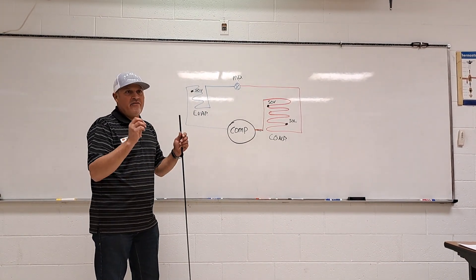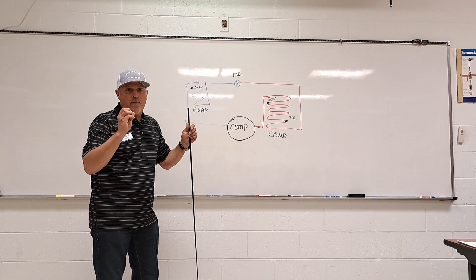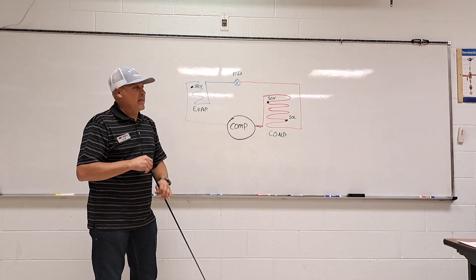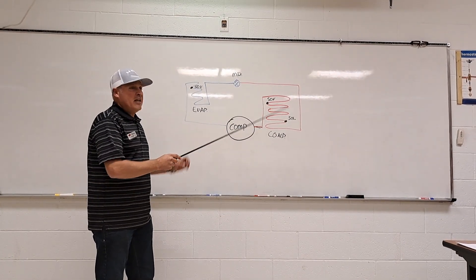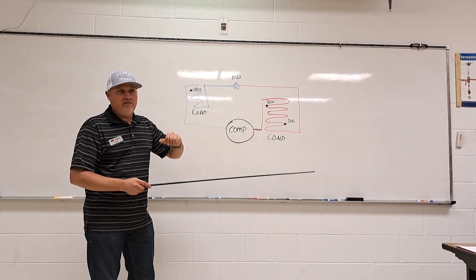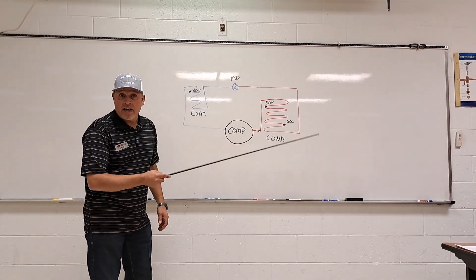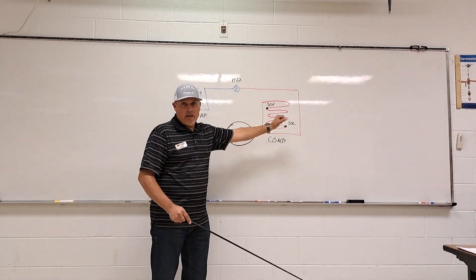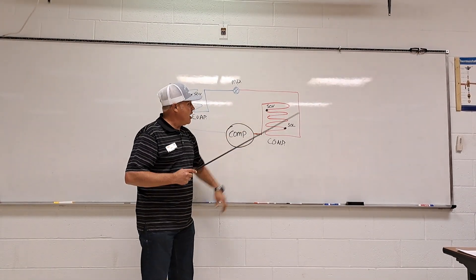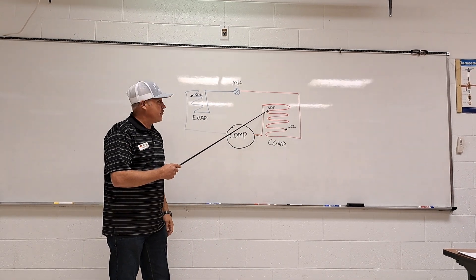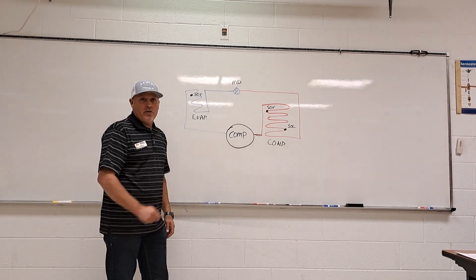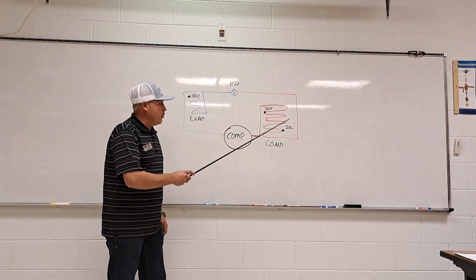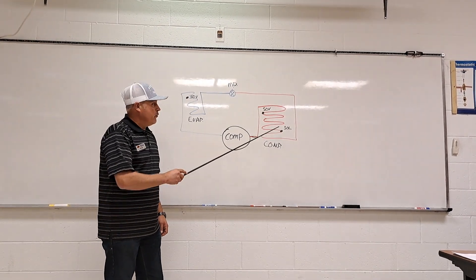A way to look at that is it's a very saturated foggy day or morning where with any cooling of temperature it will start to rain. So in the condenser, we are giving up latent heat causing the refrigerant to change from a vapor to 100% liquid. At this point, saturation point of liquid, we will begin to subcool.